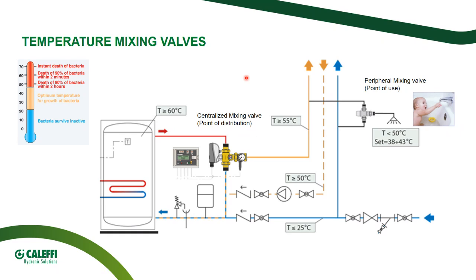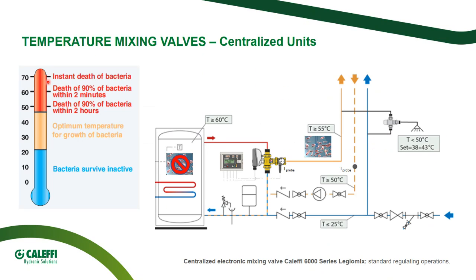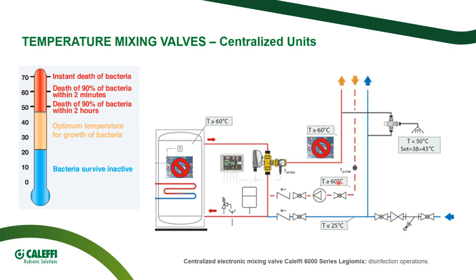Okay, but in terms of code, really, you distribute at 60 degrees, and then you return back from the furthest point at 55 and back to the main storage tank at, let's say, 50 degrees. Technically, it is feasible, but for a matter of safety, it is not recommended, and some European standards also don't recommend it. So the achievement of a certain temperature value in the distribution system shall be reached just for some minutes during the thermal disinfection.